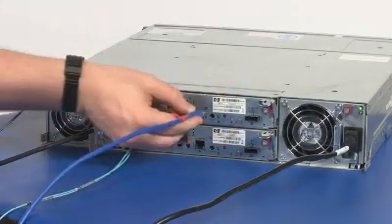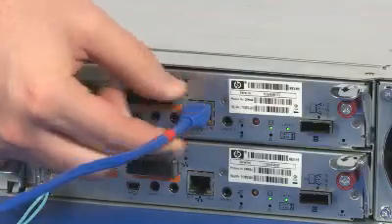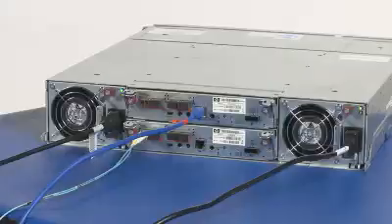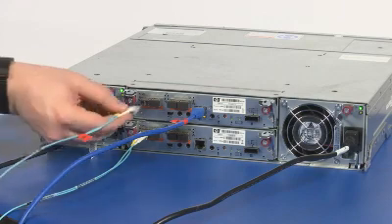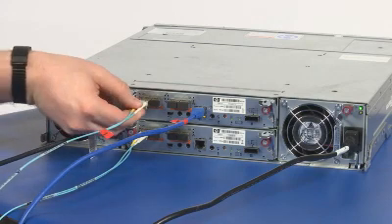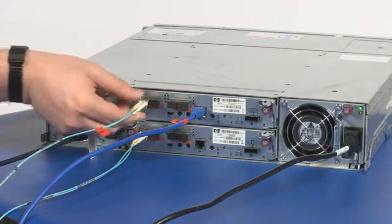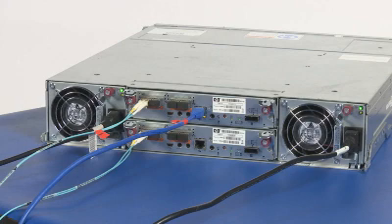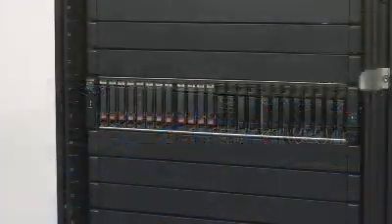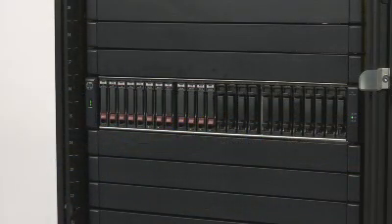Reconnect the cables. After installing a controller in an operational dual controller system, the new controller automatically begins initializing. If the firmware versions differ between the two controllers, the Partner Firmware Update feature brings the older firmware to the later firmware level.